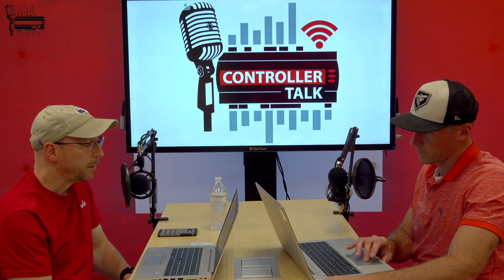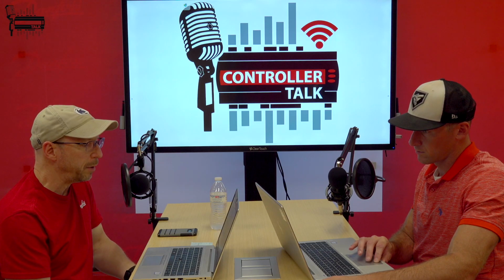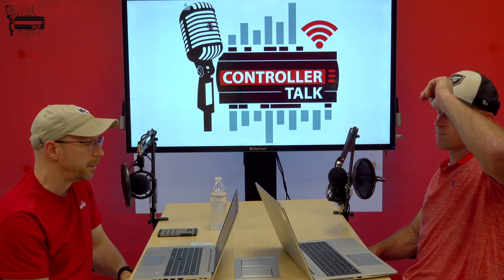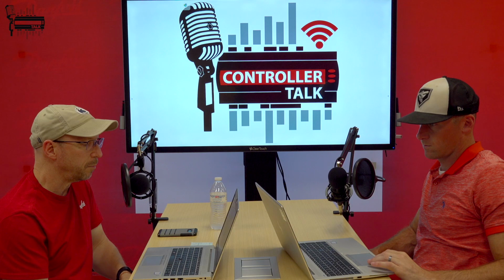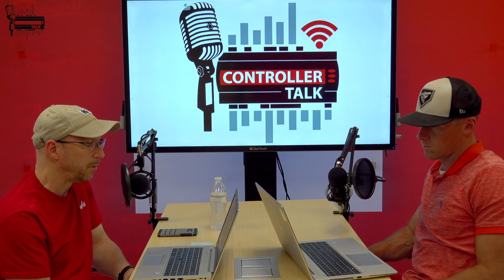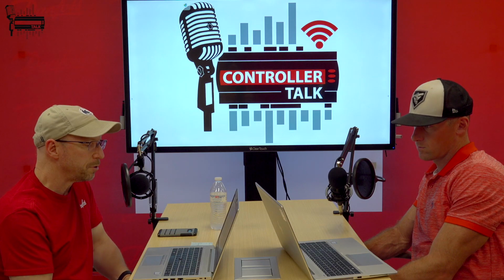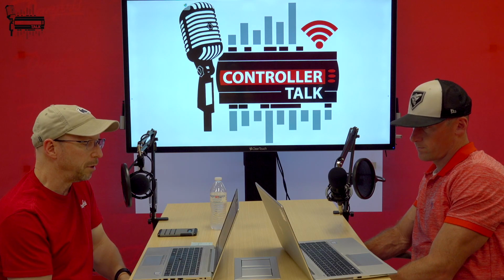Right. Okay. Yep. So the most widely used CO2 pack controller that we have right now is the 782A and 782B. And the only difference between those two is the communication, meaning that on the A version, communication back to the system manager, which is typically the 800A now, is going to be through an Echelon RS485. But when you go to the 782B, it's going to have a different cover on it, and communication is via like a Cat6 IP through a router and then into the bottom Ethernet port on the 800A. That's the one that some people use by mistake, or they're not quite sure what we are going to use this for. Well, that's its purpose there.